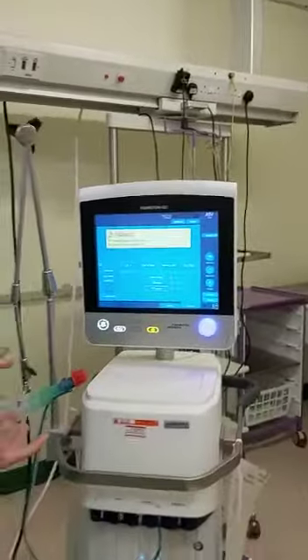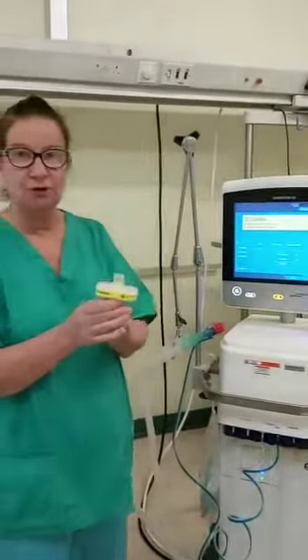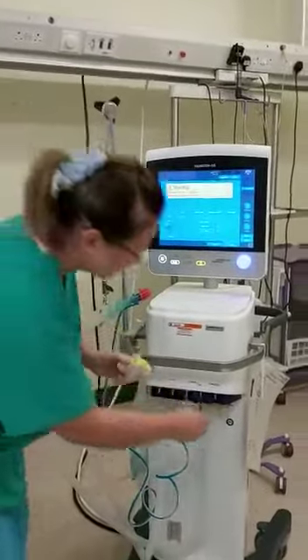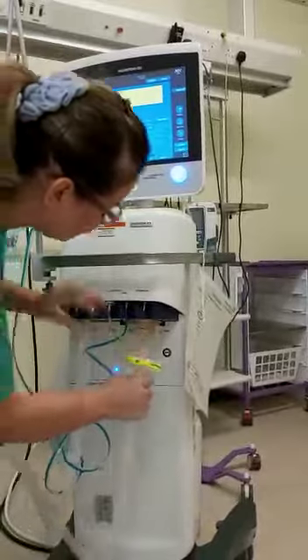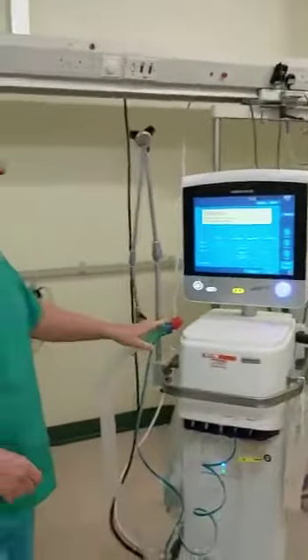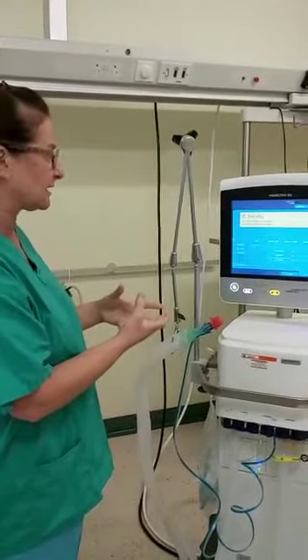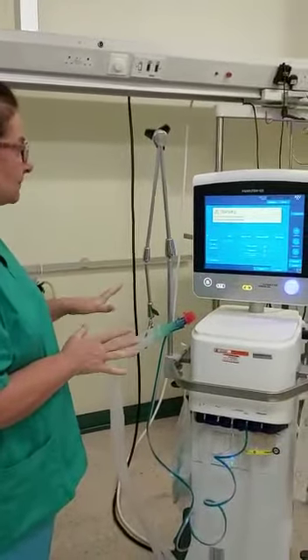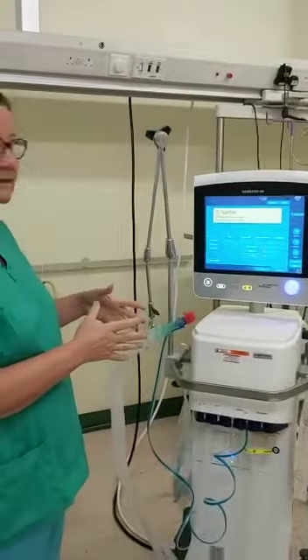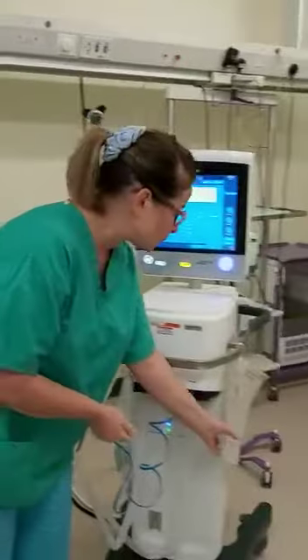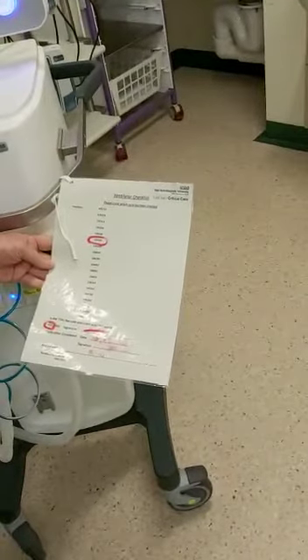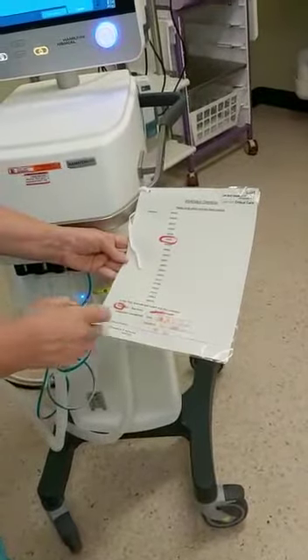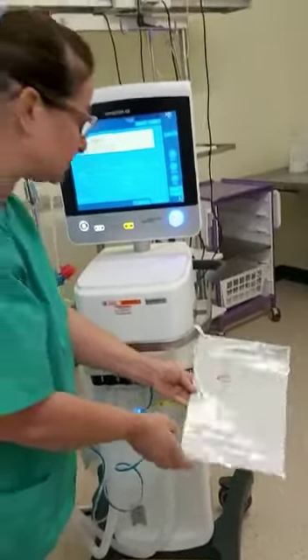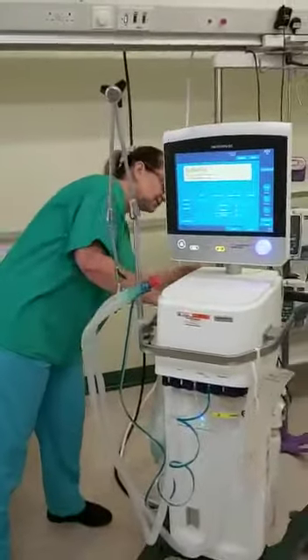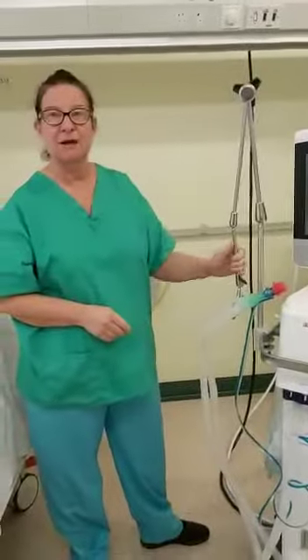If we were now going to use this on a patient, it's important to remember that you need to put your bacterial filter between the ventilator circuit and your expiratory valve. So that goes on here like so, and then you would be able to attach your suction tubing, catheter mount, etc. ready for patient use. If you don't want to use the ventilator now, we've just calibrated it so that we know it's clean and ready to use. What you will do is update the ventilator checklist at the side. So make sure that you've got the corresponding asset number here, and then we will sign to say that it was calibrated and who calibrated it and whether there were any issues. And once you've done that, then you can just turn it off, just leaving it plugged in and ready for when it might be needed.